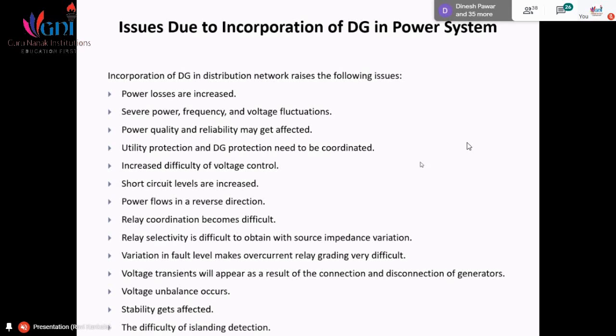Then relay selectivity is difficult to obtain with source impedance variation. Because of the introduction of this DG, what will happen? Your source impedance is going to change because earlier you had conventional sources and now you have introduced another source on the distribution side. So definitely the source impedance is going to vary and that is going to cause difficulty for a relay in having selectivity. तो आपका जो रिले है उसकी सिलेक्टिविटी जो है दैट इज गोइंग टू बी अफेक्ट because of the variation in the source impedance because of the introduction of your DG into a system. That is called relay selectivity. It becomes difficult in that case.